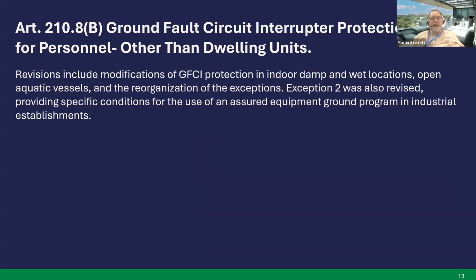Article 210.8(B), ground fault circuit interrupter protection for personnel other than dwelling units. Similar to the dwelling units, there were some modifications of the GFCI protection in indoor damp and wet locations, open aquatic vessels, and the reorganization of the exceptions. There was nothing added. It was just formatted differently now, more clear. Exception 2 was also revised, providing specific conditions for the use of an assured equipment grounding program in industrial establishments. Next slide.